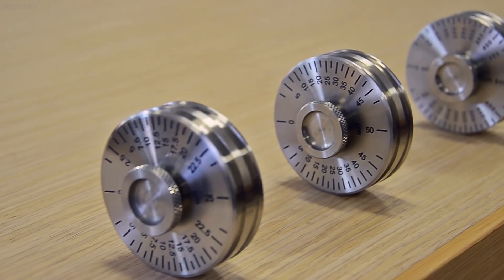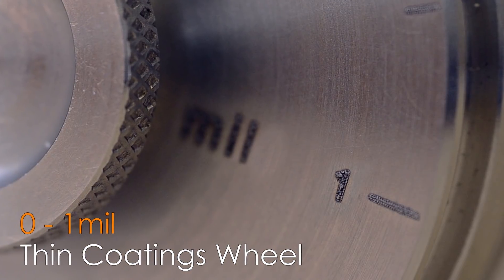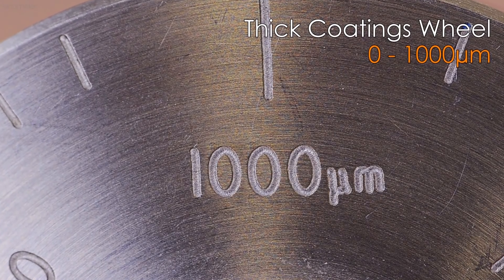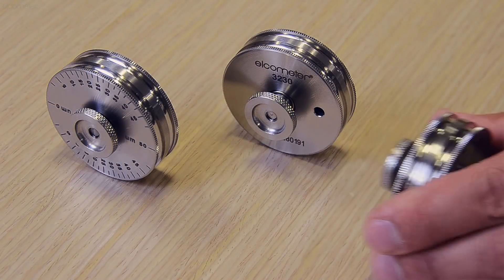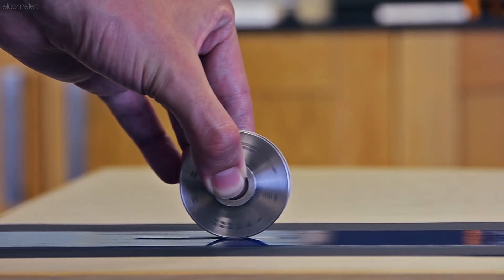The Elcometer 3230 wet film wheels are available in a wide range of scales, from the 0–25 microns (or 0–1mil) thin coatings wheel, to the thick coatings wheel which measures wet film thicknesses up to 1000 microns or 40 mil. In addition to the standard wheels, Elcometer also offers a number of wet film wheels specifically designed for in-line wet film measurements. The Elcometer 3230 coil coating wet film wheels have knurled outer wheels, which minimise skipping, thereby allowing measurements to be taken on fast-moving substrates.